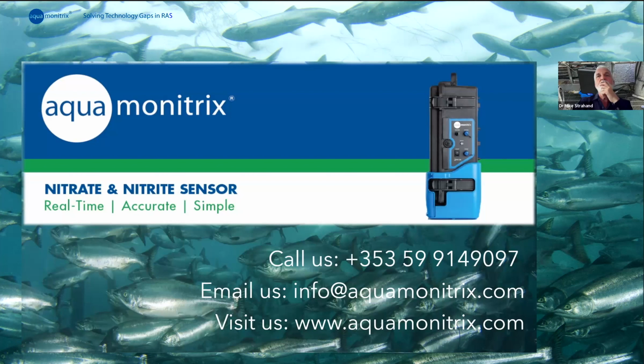Okay, and just one thing I would add to that as well. The other thing I think we found, Eoin, was that when we do change the columns, it doesn't have a detrimental effect on the accuracy of the instrument. We at first thought changing a column would necessitate a calibration, but I don't think we've even found that, have we? Yeah, exactly. That's what I was just saying there, Mike. There's no need to recalibrate.